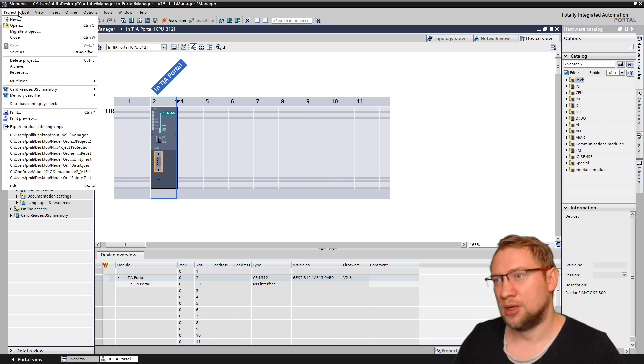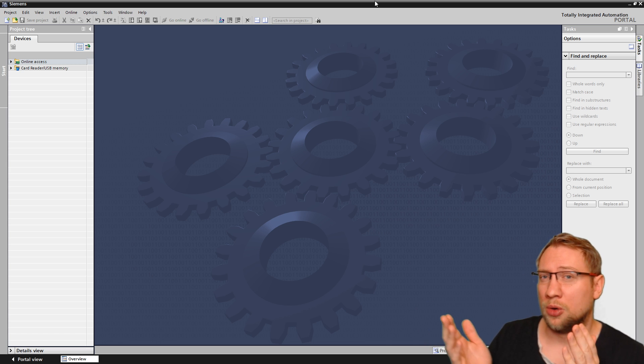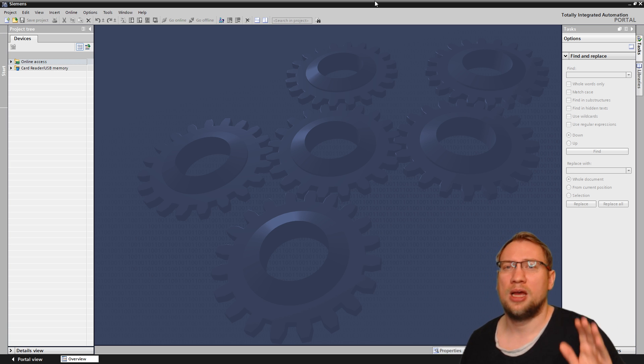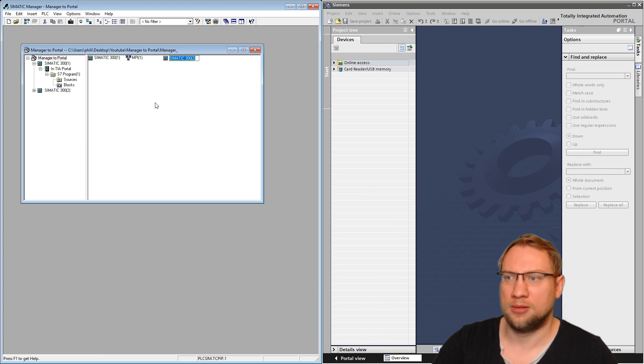So the checkbox activates the hardware configuration migration. Now the question: why does that strange checkbox exist? It exists because hardware — PLCs, I/O modules, and so on — that was cancelled before approximately November 1, 2007 or 2008, is not in TIA Portal. Everything produced from that date onward, or produced prior but still being produced after it, is in TIA Portal. Everything cancelled earlier is not. This is why some hardware is simply not available in TIA Portal.